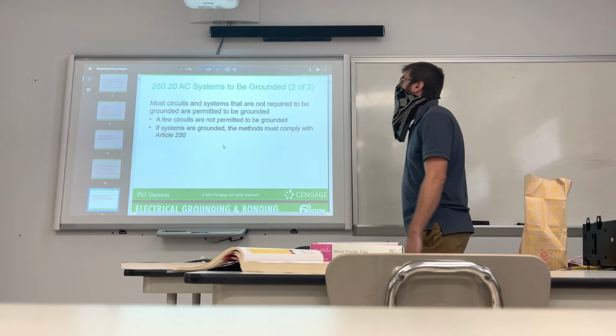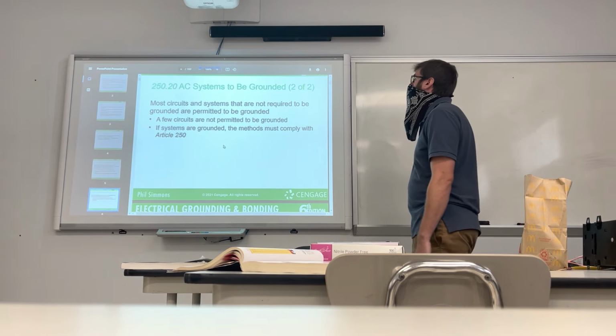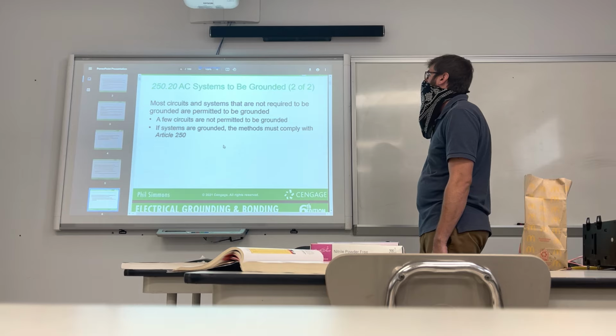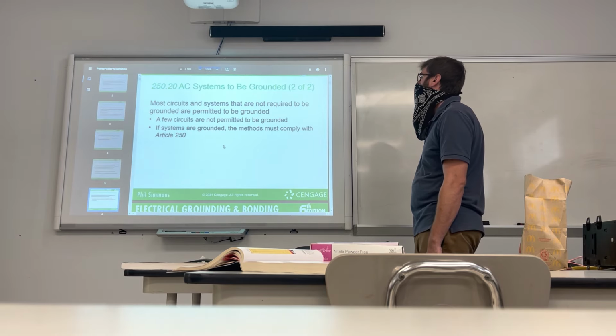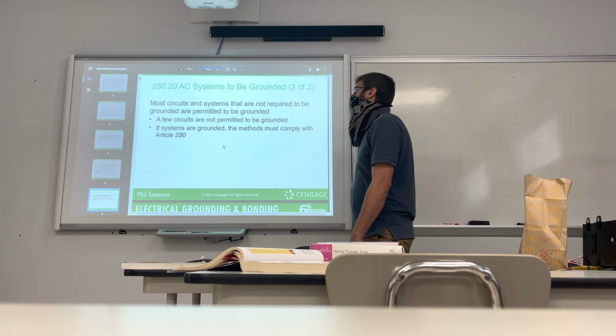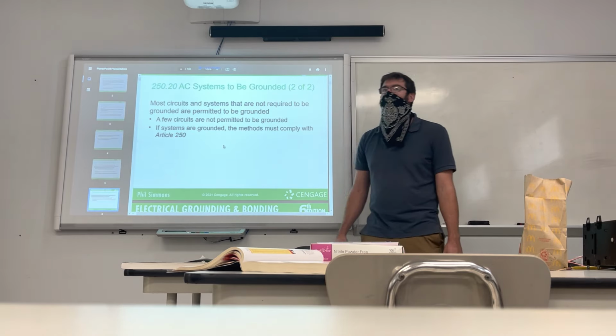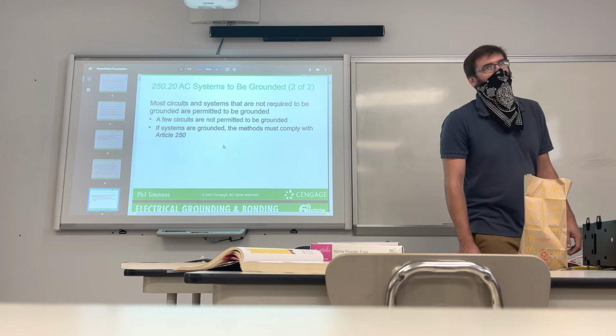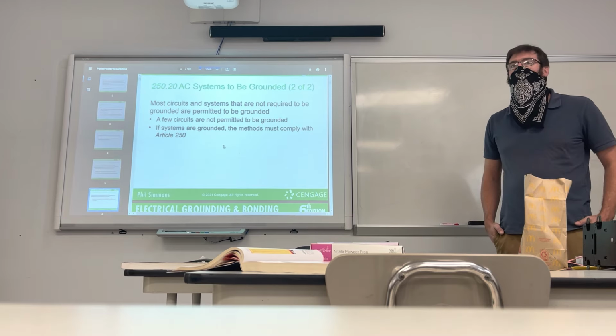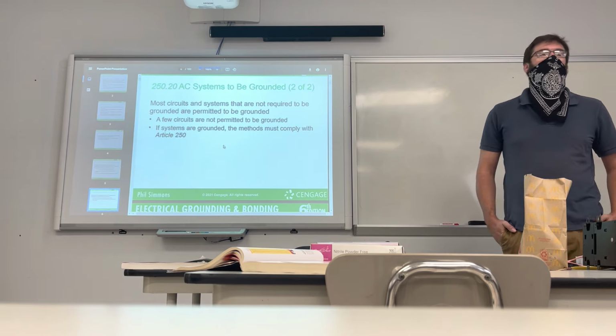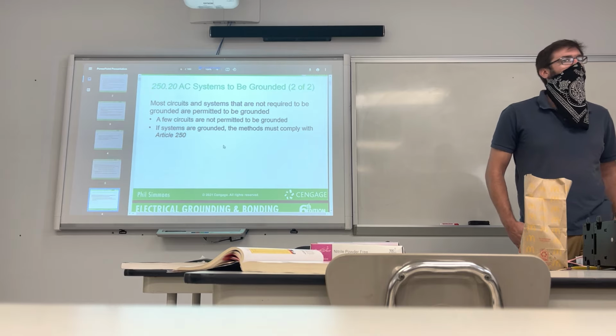Most circuits and systems that are not required to be grounded are permitted to be grounded. A few circuits are not permitted to be grounded. If systems are grounded, the methods must comply with Article 250. Okay, so give me an example of a system that shouldn't be grounded. We talked about this last class. Just give me one example of a system that should not be grounded.